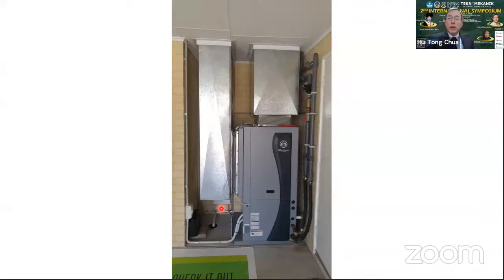This is the ground source heat pump, which, as I alluded to earlier, resides at the corner of the double lockup garage. This ducting here returns the room air to the heat pump, and after the air conditioning treatment here, the conditioned air is sent via this duct back into the indoor environment. So these two pipes here supply and return the groundwater.